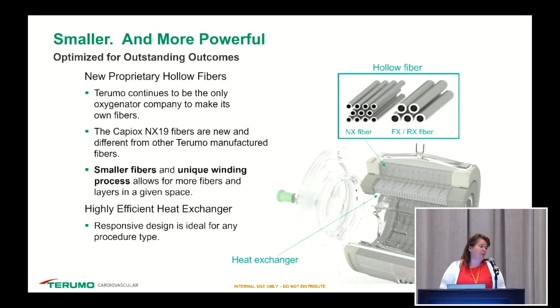As the video alluded to, the hollow fibers are smaller and more powerful. So it is new proprietary hollow fibers. We continue to be the only oxygenator whose company makes the hollow fibers within Terumo, so that we're able to design them as we need them to be, to work the way that we choose them to work. So the fibers are new, they're different from the other manufactured fibers that we've used before. They are smaller, they have a unique winding process, and they allow for more fibers and layers in a given space. So the heat exchanger, as mentioned, is highly efficient, and its responsive design is ideal for any procedure type such as circ arrest.